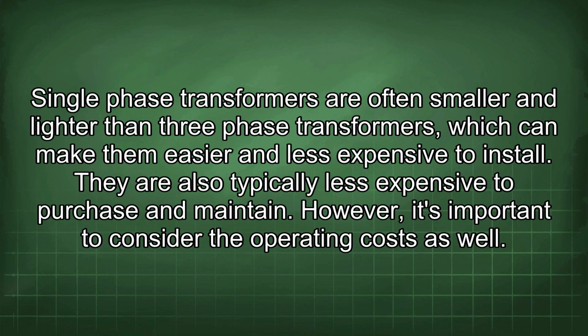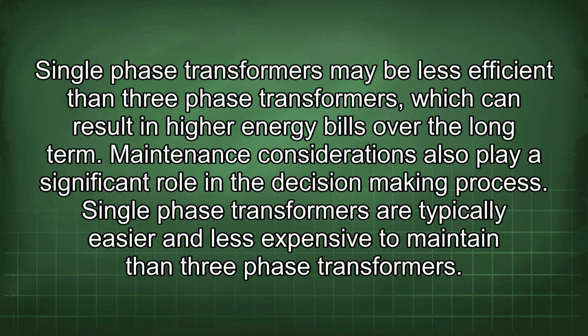Single-phase transformers are often smaller and lighter than three-phase transformers, which can make them easier and less expensive to install. They are also typically less expensive to purchase and maintain. However, it's important to consider the operating costs as well. Single-phase transformers may be less efficient than three-phase transformers, which can result in higher energy bills over the long term.